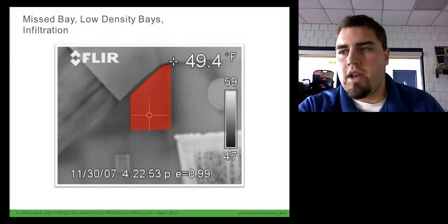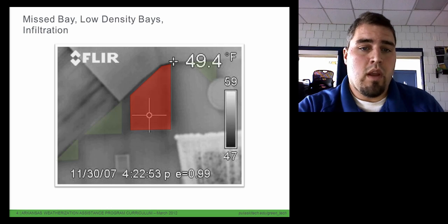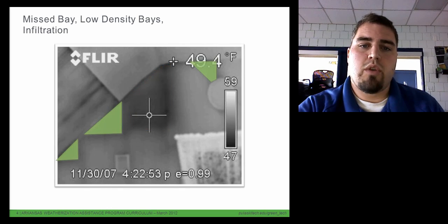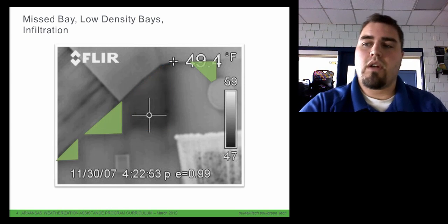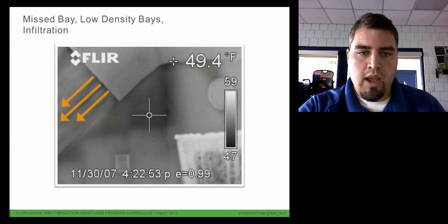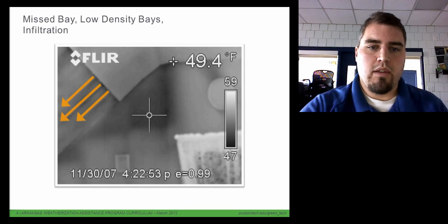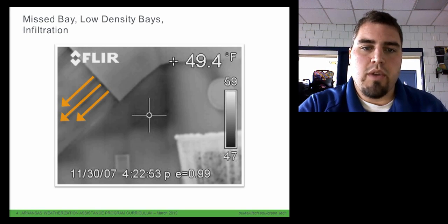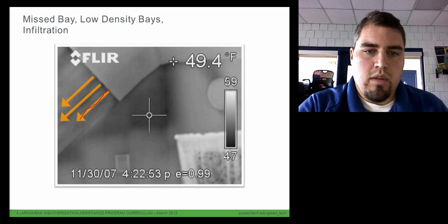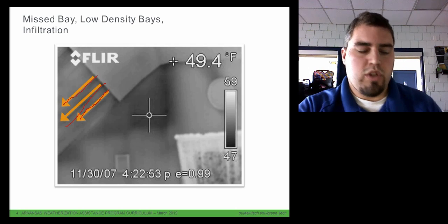All right, move our red in, showing our missing insulation, and then our pea green, showing you where insulation was improperly installed. And then our streaks, y'all can't see my finger on the screen, can you? Our streaks here where the air is coming between the sheetrock and the lath and plaster.